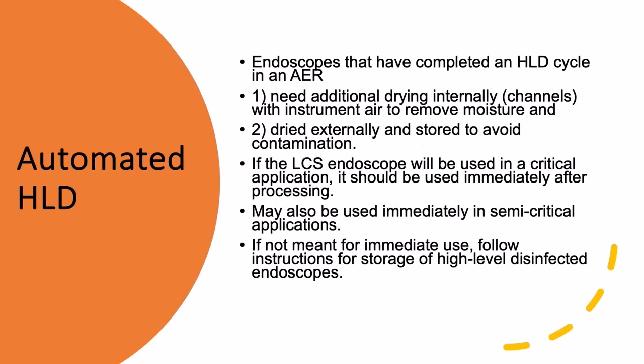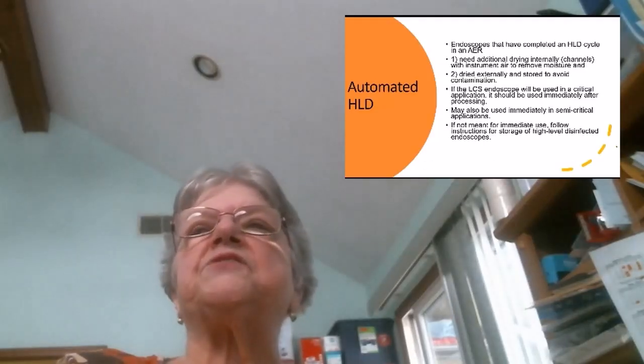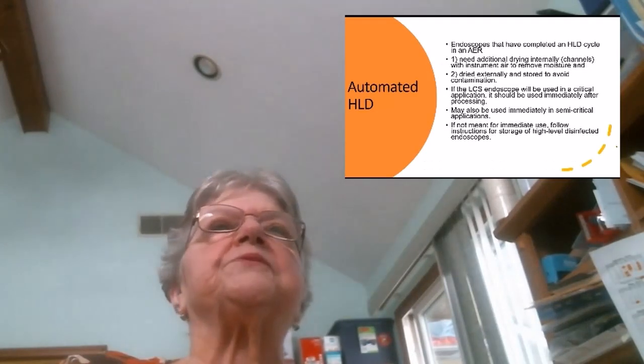Endoscopes that have completed a high-level disinfection cycle in an AER need additional drying of the internal channels with instrument air to remove moisture, and also need to be dried externally and stored to avoid contamination. Your AERs have a purge cycle that is not the same as drying. If the liquid chemical sterilant endoscope will be used in a critical application, such as in a surgical field, it should be used immediately after processing. It can also be used immediately in a semi-critical application. If it's not going to be used immediately, follow the instructions in the document for storage of high-level disinfected endoscopes.